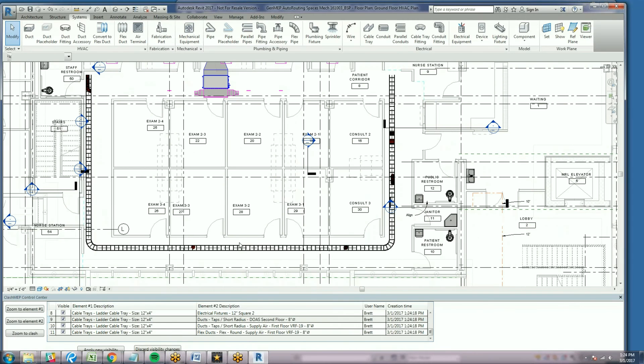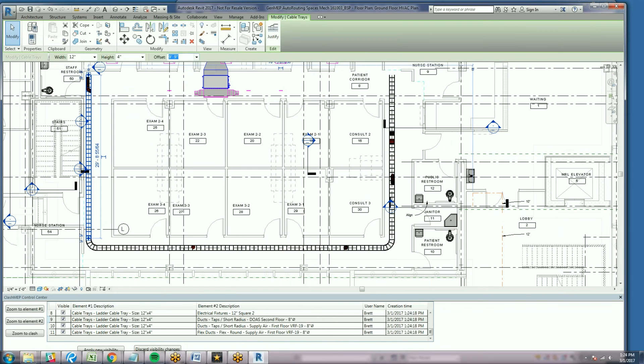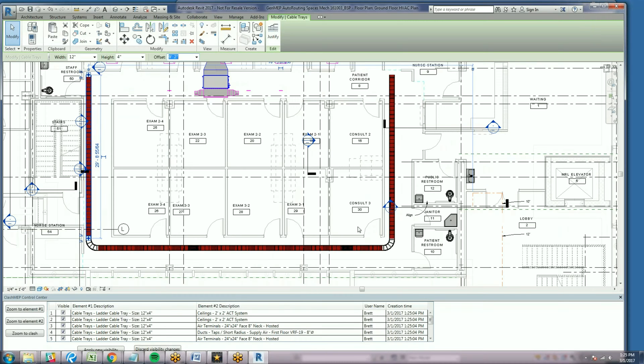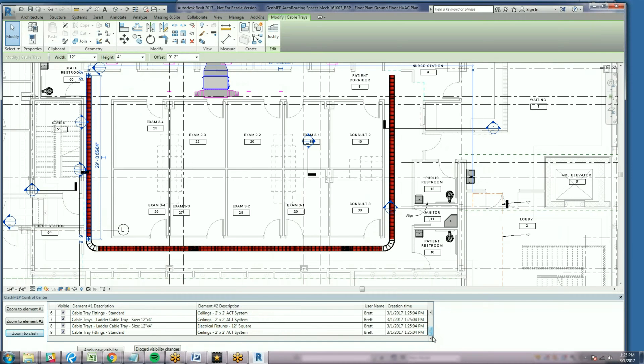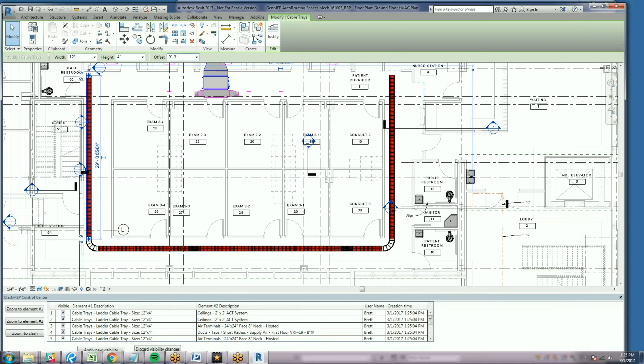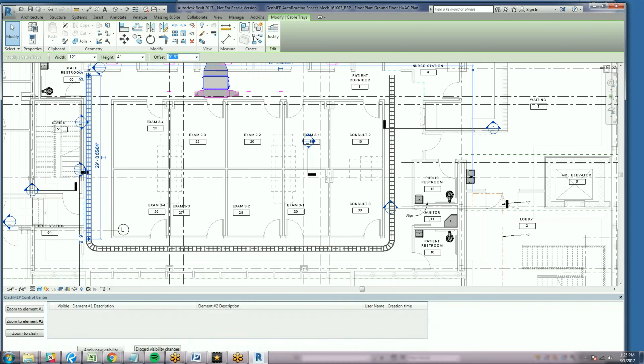Since this is a cable tray, we know that access is important. We lower the entire cable tray route to see if we have more or fewer clashes. Immediately, we see that we're clashing with the ceiling and the new lower elevation is not viable. The clashes in this model are dynamically updated. We try several elevations and finally find an acceptable elevation.